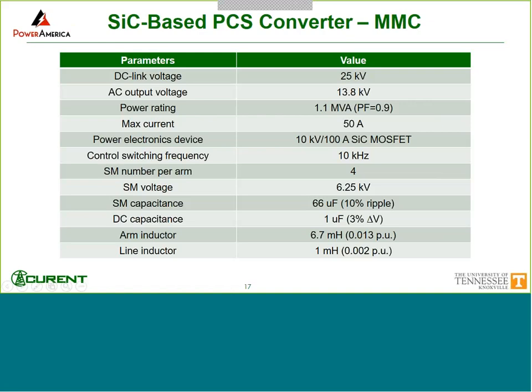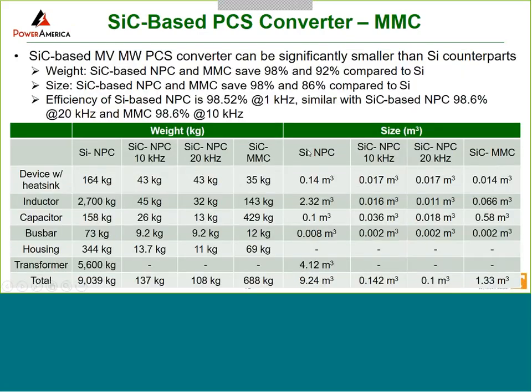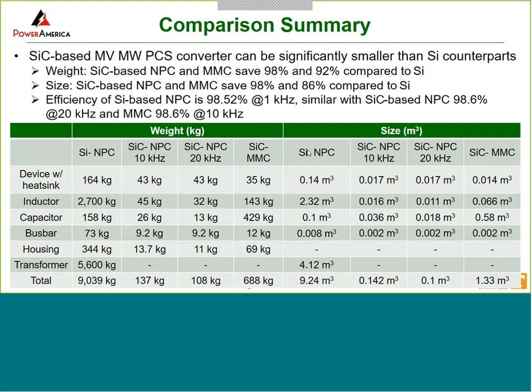MMC is similar, and so these are the different line parameters. And in the case of MMC, we only need to do 10 kilohertz, and we use four submodules per arm. Again, this is a 10 kV device. So this shows the actual comparison of the three different designs, actually four, because NPC we have two different switching frequencies, and they all are meeting the same converter requirement.